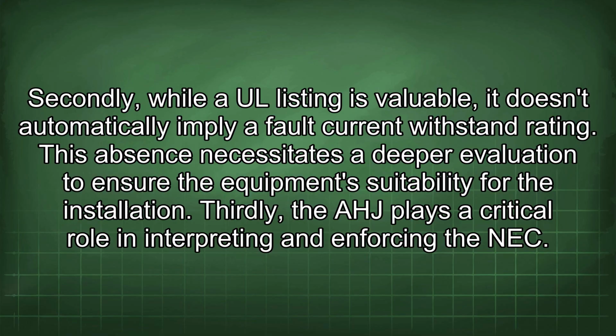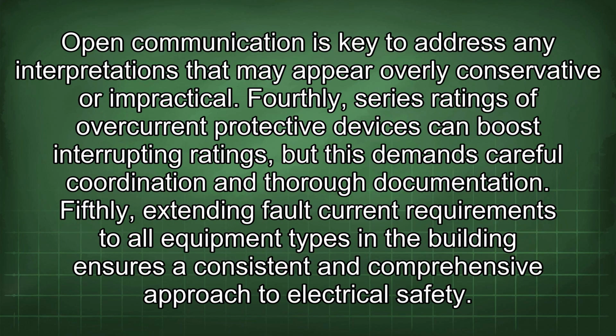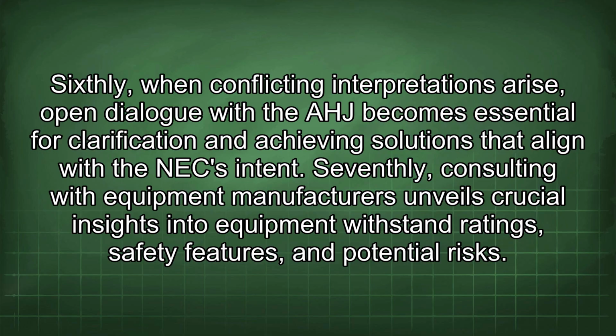Thirdly, the AHJ plays a critical role in interpreting and enforcing the NEC. Open communication is key to address any interpretations that may appear overly conservative or impractical. Fourthly, series ratings of overcurrent protective devices can boost interrupting ratings, but this demands careful coordination and thorough documentation. Fifthly, extending fault current requirements to all equipment types in the building ensures a consistent and comprehensive approach to electrical safety. Sixthly, when conflicting interpretations arise, open dialogue with the AHJ becomes essential for clarification and achieving solutions that align with the NEC intent.